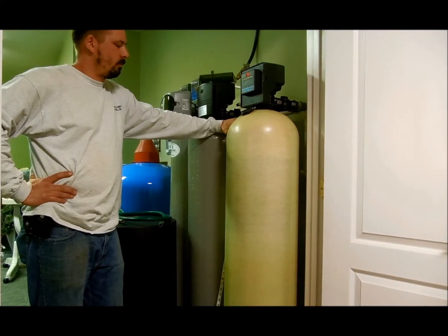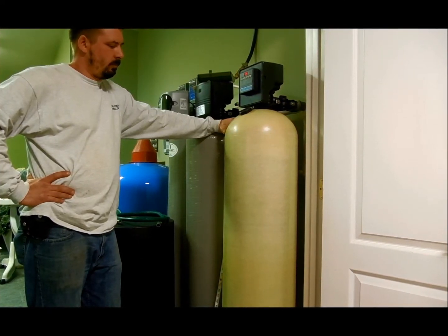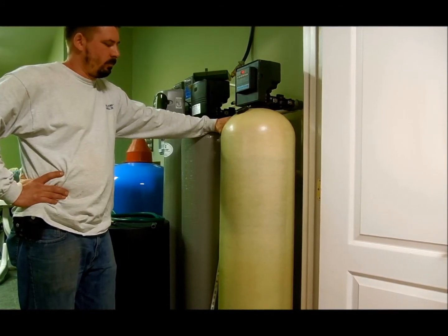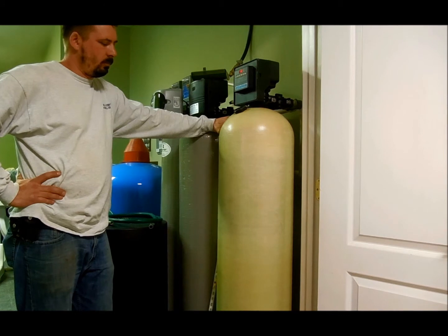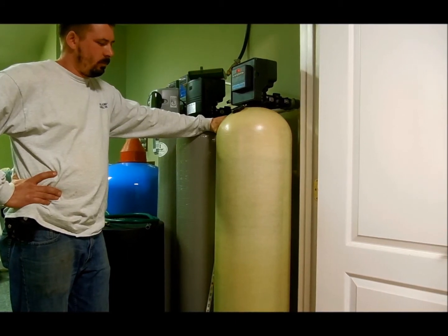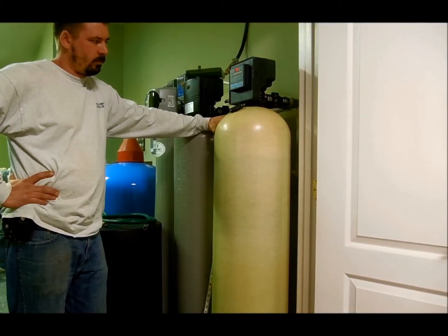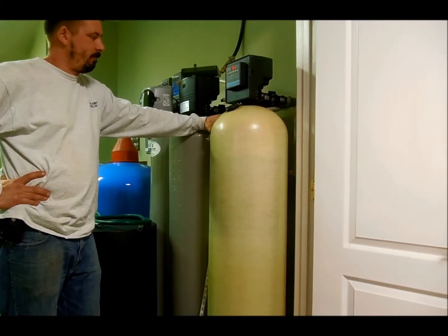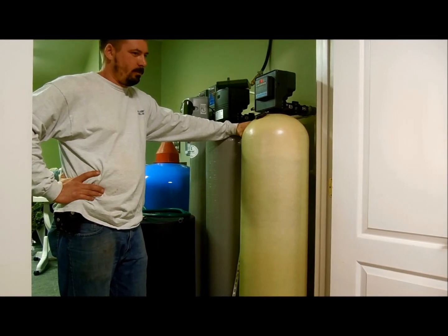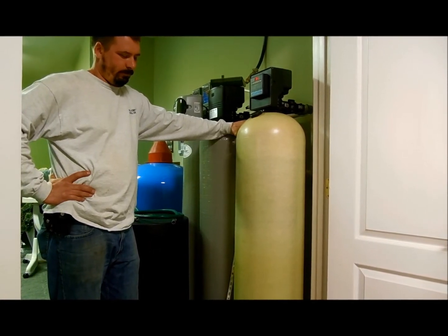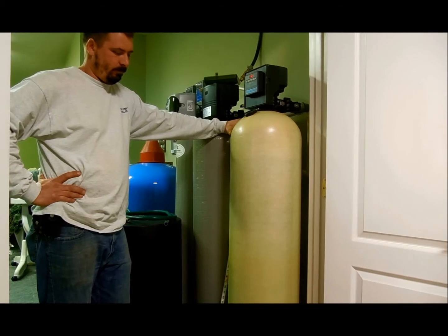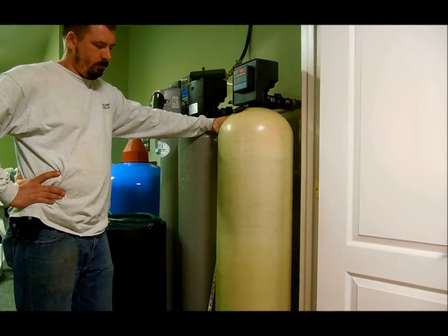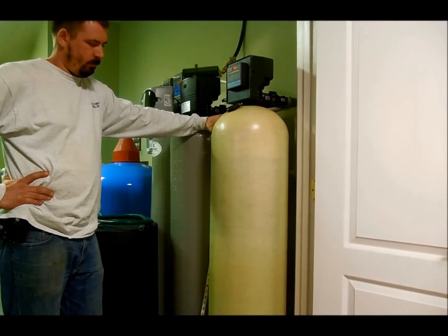There are several ways the pH can be corrected. The method we are using here today is running the water through a calcite bed. Depending on the severity of the acidity, the tank has to be properly sized so that the water touches the calcite long enough to bring the pH to a 7 or above. This has to be calculated by investigating the highest possible usage in the house and matching that with the flow constraints for the filter itself. That's determined by the manufacturer.